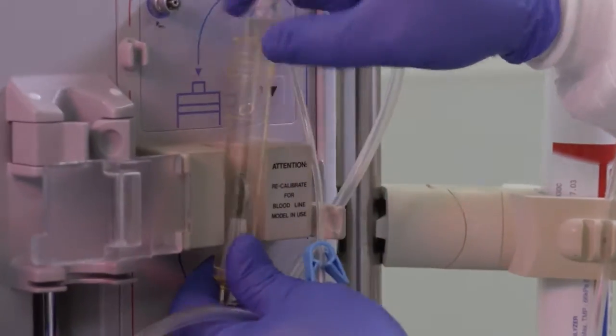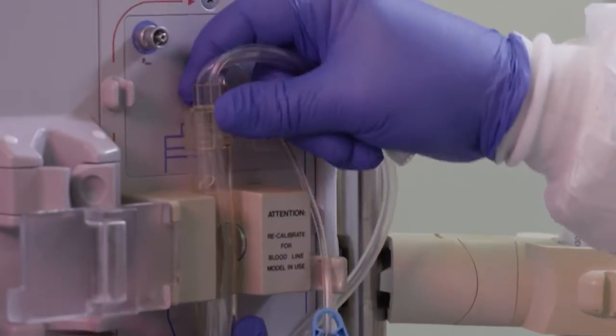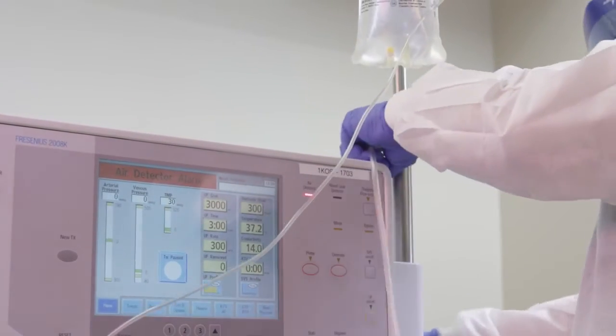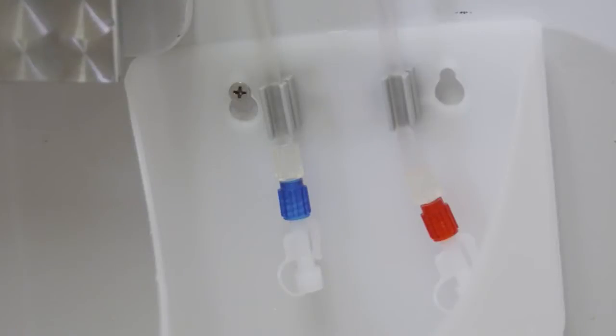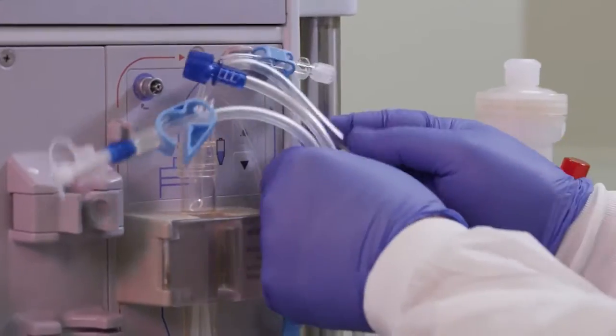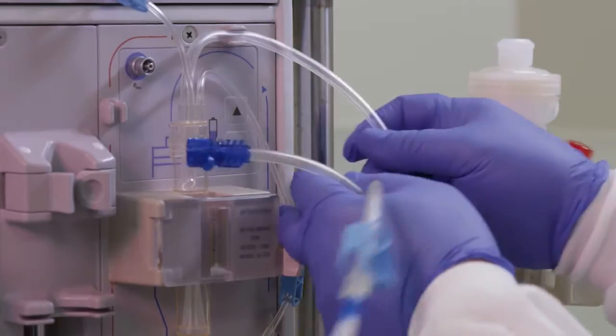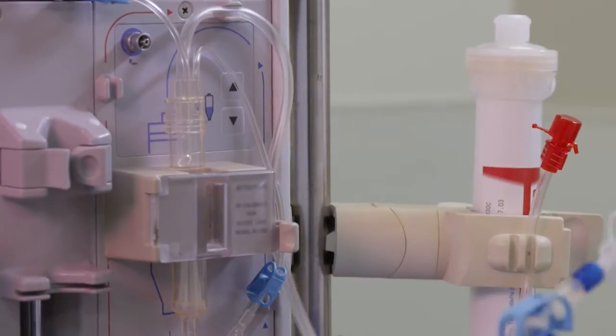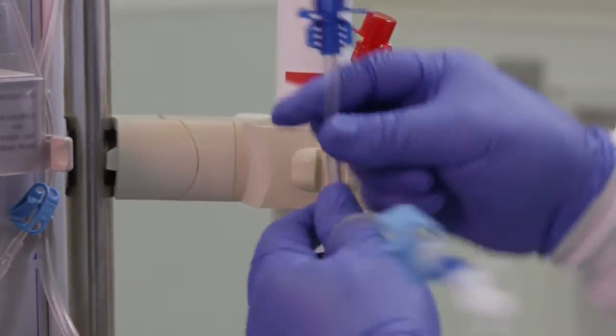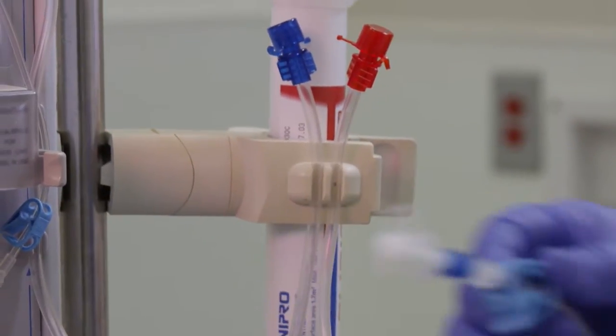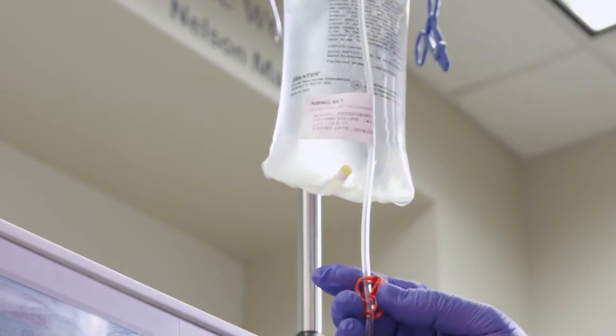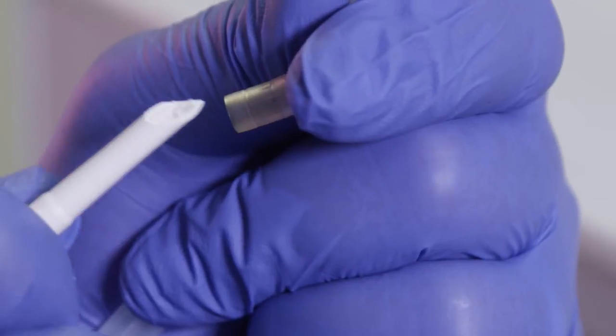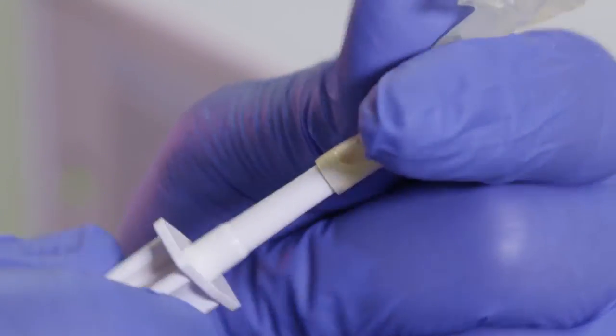Place the venous drip chamber in the air detector with the filter just below the silver pads. Place the patient end of the tubing into the priming container, verifying that the end of the line does not come in contact with the container. Close all small clamps on the venous blood line. Finish threading the venous line into the appropriate line clips on the front of the machine. Place the dialyzer end of the venous blood line into the appropriate groove or clip on the dialyzer holder. Clamp the IV administration line and aseptically spike a liter bag of 0.9% saline.